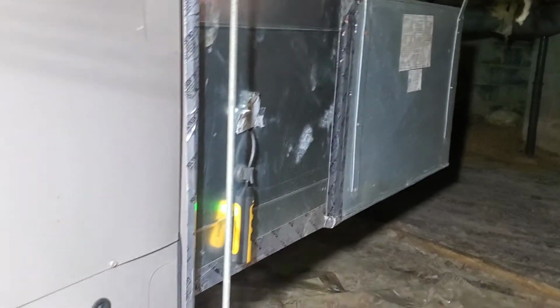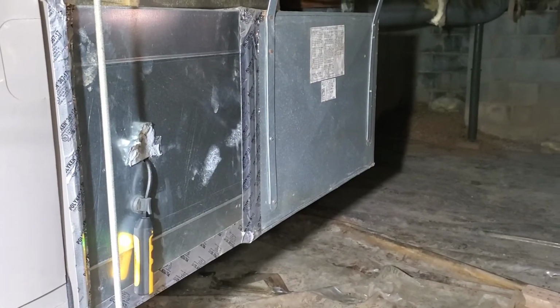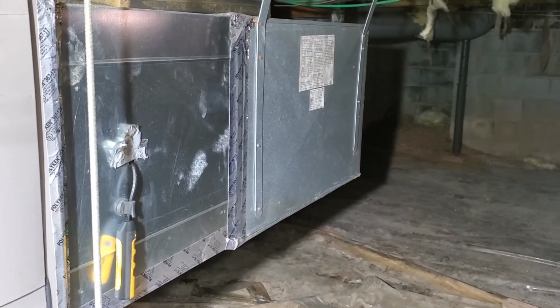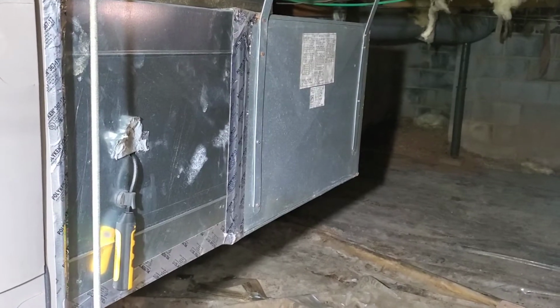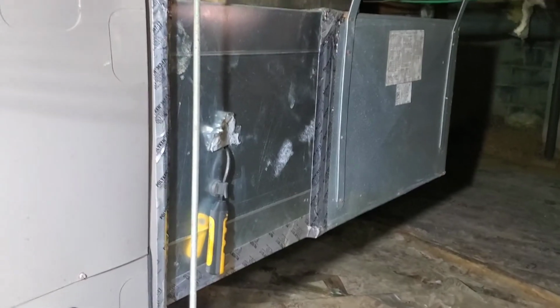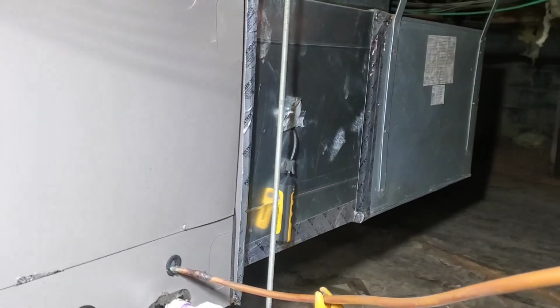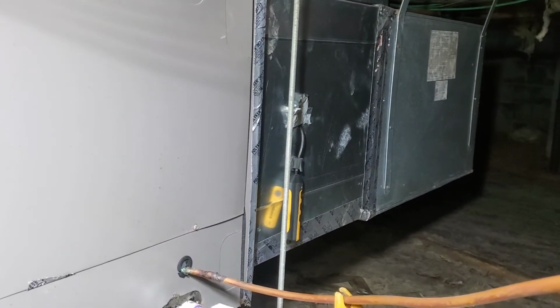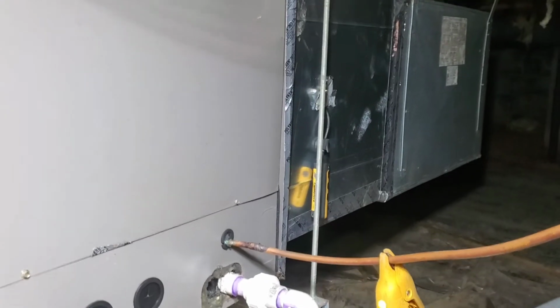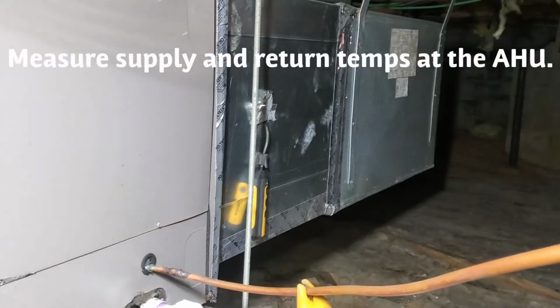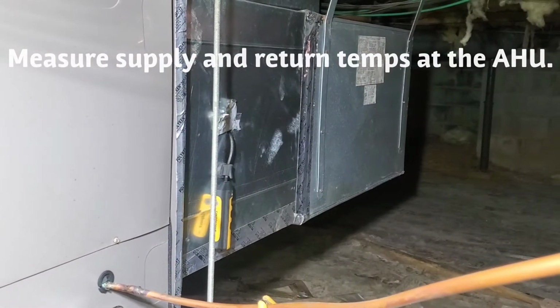And so you're not really seeing what the refrigerant sees when you measure your return air temperature at the indoor grill. It could be 5 or 6 degrees warmer up there than it is where it actually hits your coil. So when we're taking our temperature readings, if you're worried about delivered capacity, then yeah, take it at your grills. But when we're charging equipment, I strongly recommend that you take your return and supply temperature coming off the equipment.